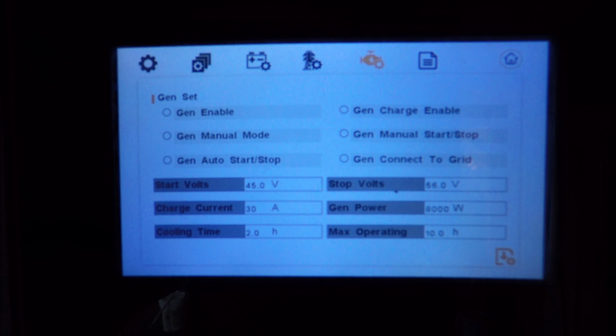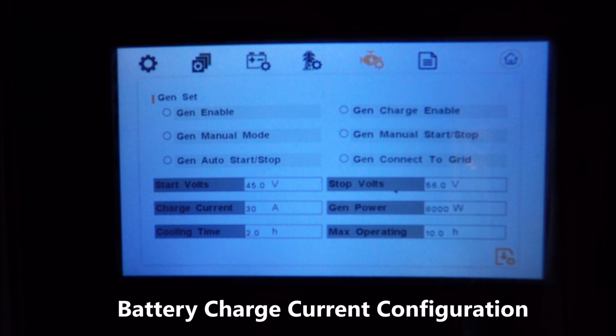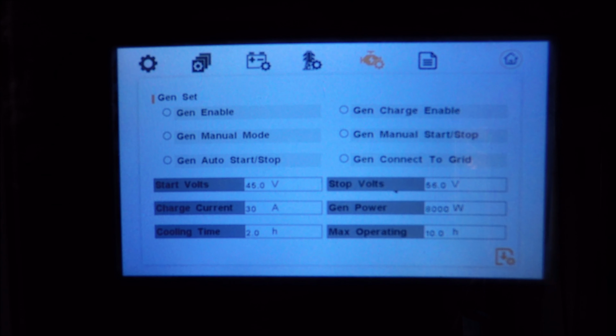If the generator supports auto start, there are inputs on the inverter to automatically start the generator. You can do it once the battery voltage hits a certain voltage, and you can stop the generator once the batteries are charged up to a certain voltage. You can set the charge current. This is very important. The charge current here is what is used to charge the batteries from the generator. Make sure the generator capacity matches this charge current.